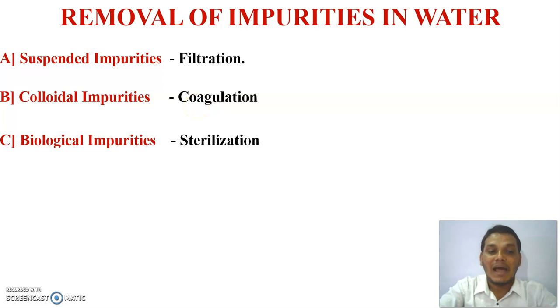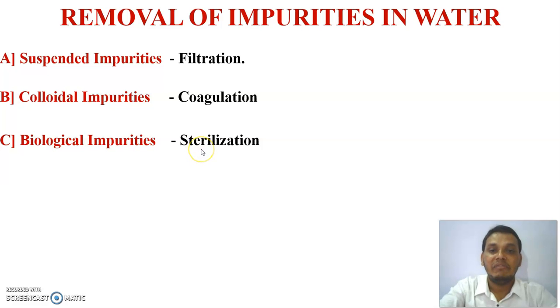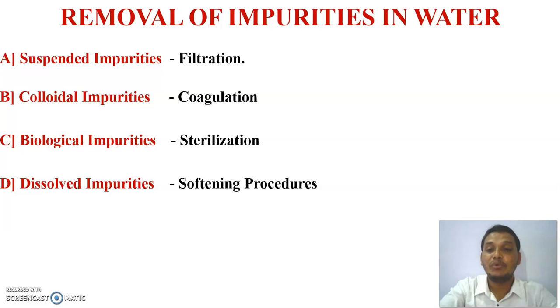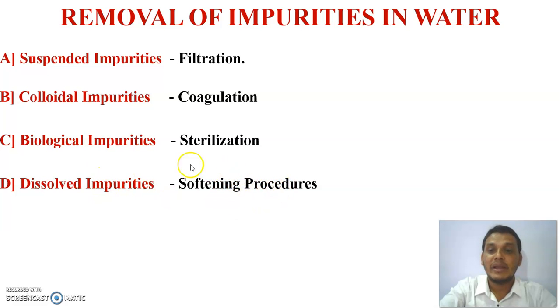Biological impurities can be removed with the help of the sterilization process. In the sterilization process, liquid chlorine and ozone are used as sterilizing agents, allowing algae, fungi, and bacteria to be easily removed. Dissolved impurities — whether dissolved salts or gases — can be removed using a water softening procedure or mechanical deaeration process.